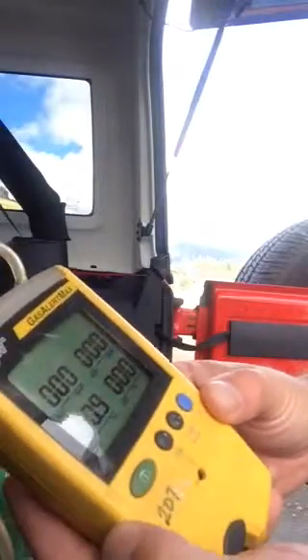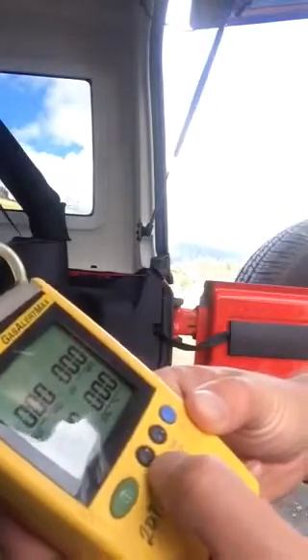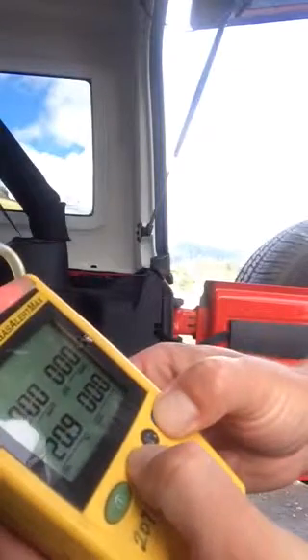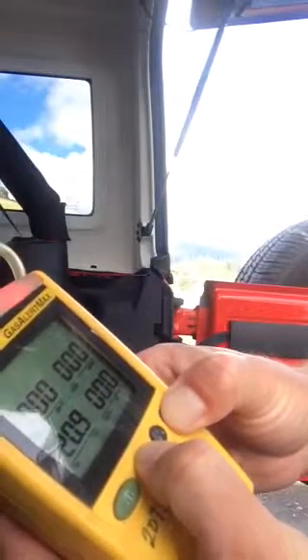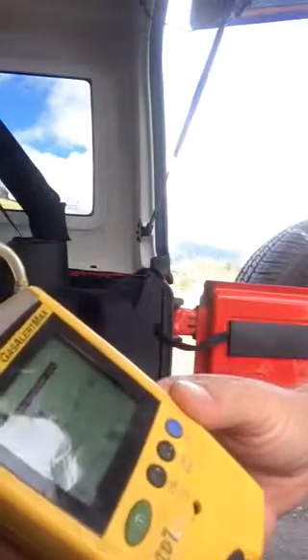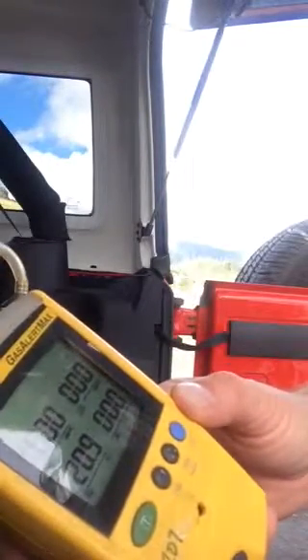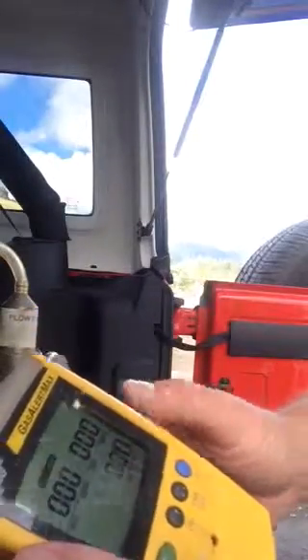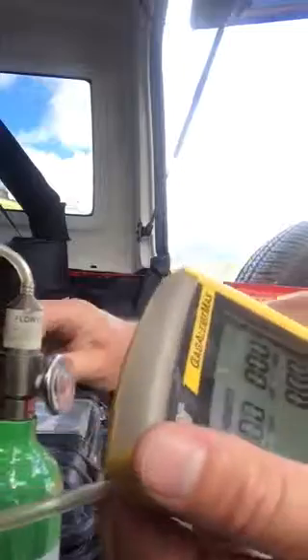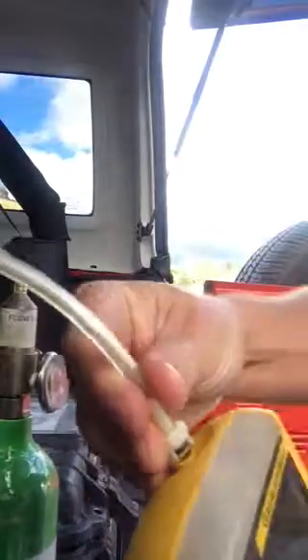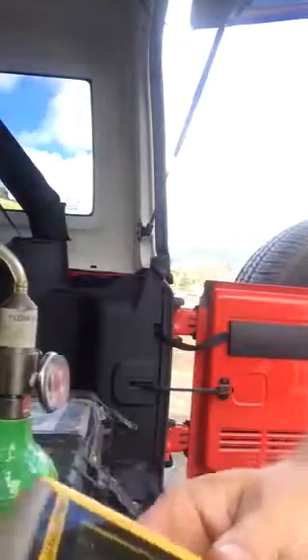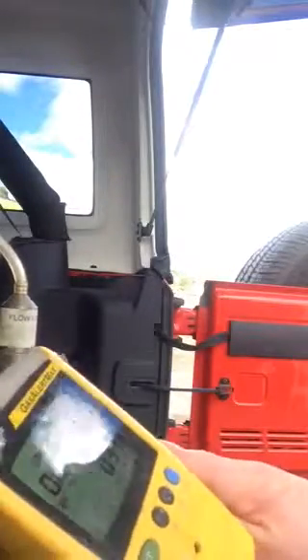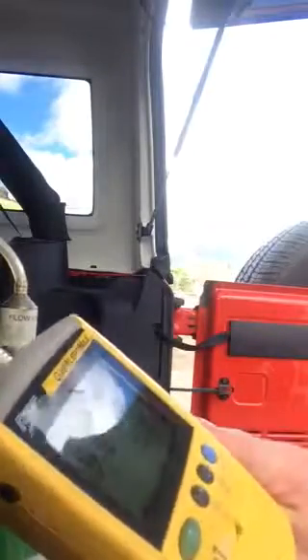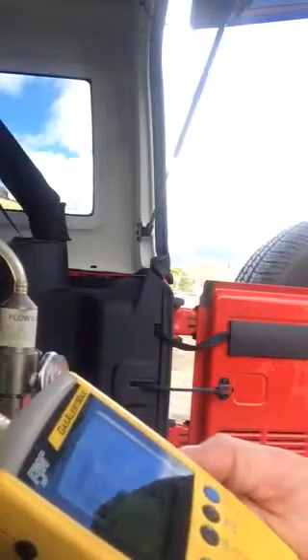Again, to go into the calibration sequence, you hit the down key and this blue key at the same time. It'll beep at you. And it'll say cal. And it zeroes out the numbers except for oxygen. And then this little ball up in the corner will start flashing. That's when you apply the gas. So turn on the gas, stick it onto the port on the back side there, and just let it do its thing. Again, you'll generally want to be away from it while it does that. It'll start beeping at you and alerting you that calibration is finished.